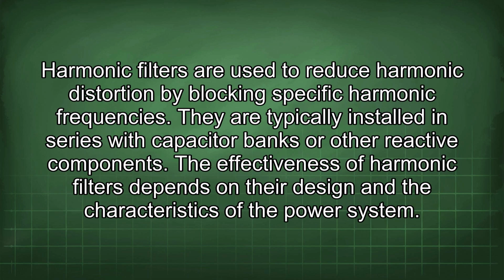Harmonic filters are used to reduce harmonic distortion by blocking specific harmonic frequencies. They are typically installed in series with capacitor banks or other reactive components. The effectiveness of harmonic filters depends on their design and the characteristics of the power system.